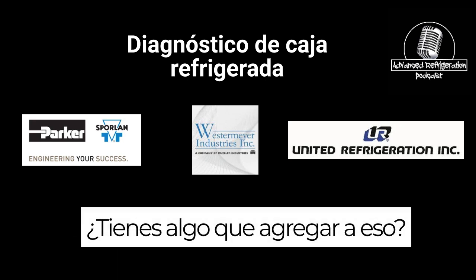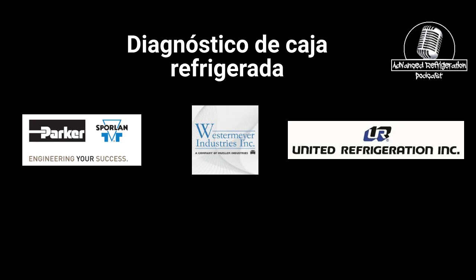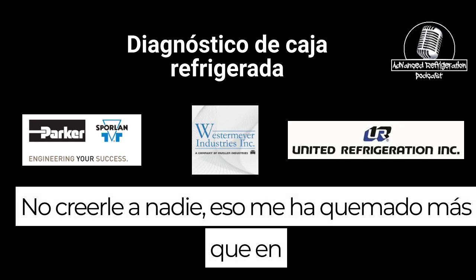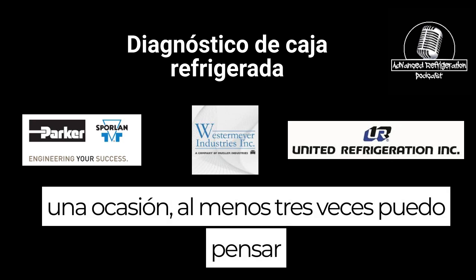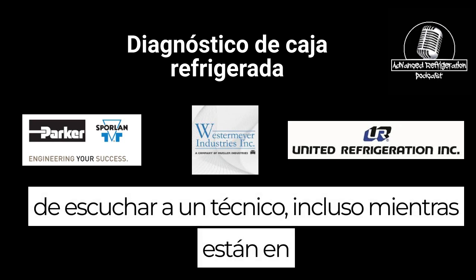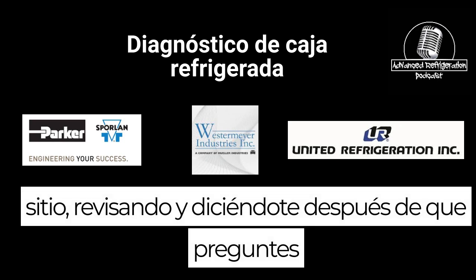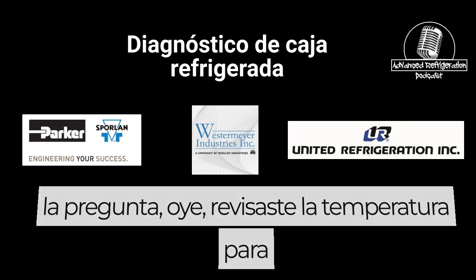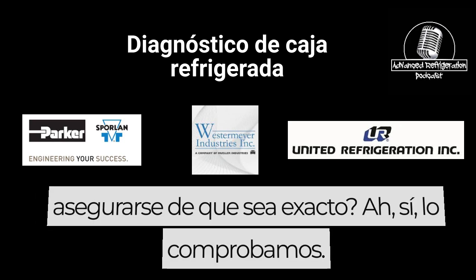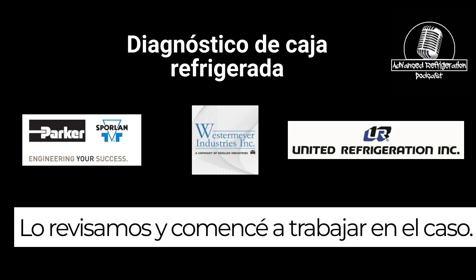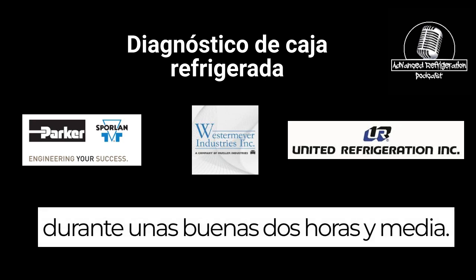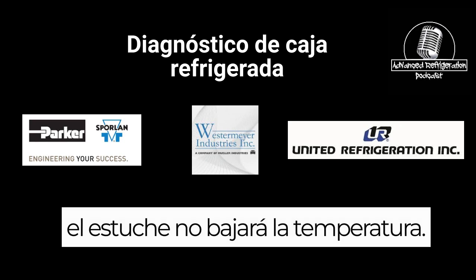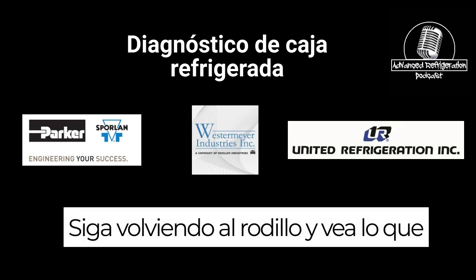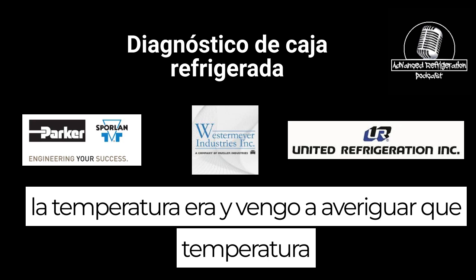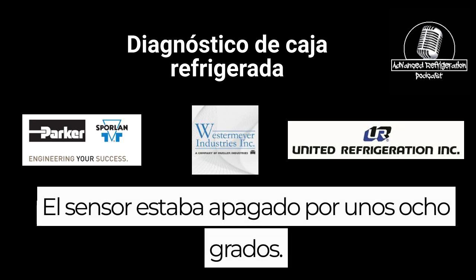You got anything to add to that, Brett? No, besides not believing anybody, because that's burned me on more than one occasion. At least three times I can think of, listening to a technician, even while they're on site, telling you after you ask the question, "Hey, did you check the temperature to make sure it's accurate?" "Oh, yeah, we checked it." And I worked on the case for a good 2.5 hours trying to figure out why this case won't pull down temperature, kept going back to the controller and seeing what the temperature was, and came to find out that the temperature sensor was off by about 8 degrees.